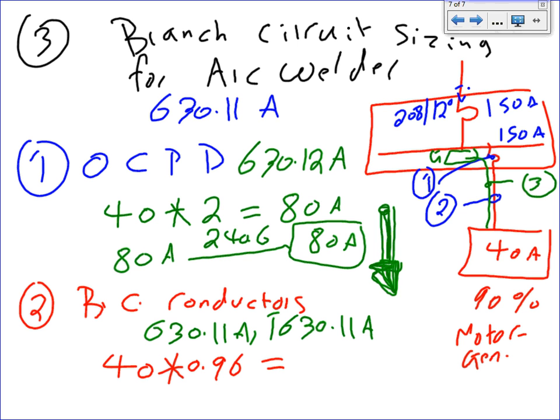Okay, can anybody give me what the answer is? 38 amps. Piece of cake. See, they allow you to apply the table to the rating. Then you take the 38 and go all the way to 310.16 or 310.15(B)(16). What size would that give you?